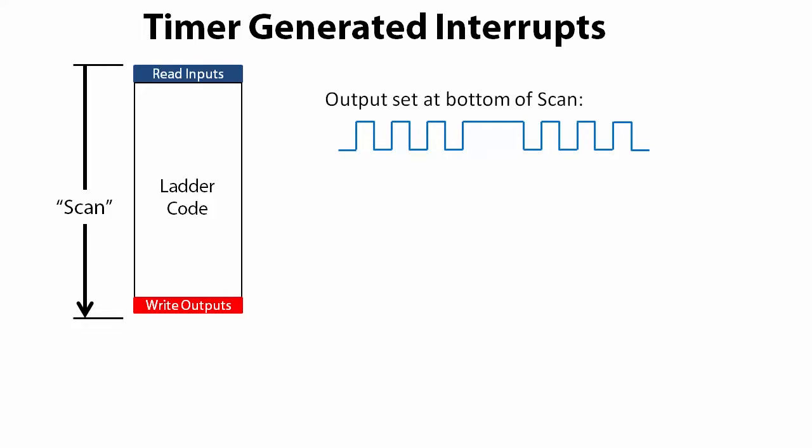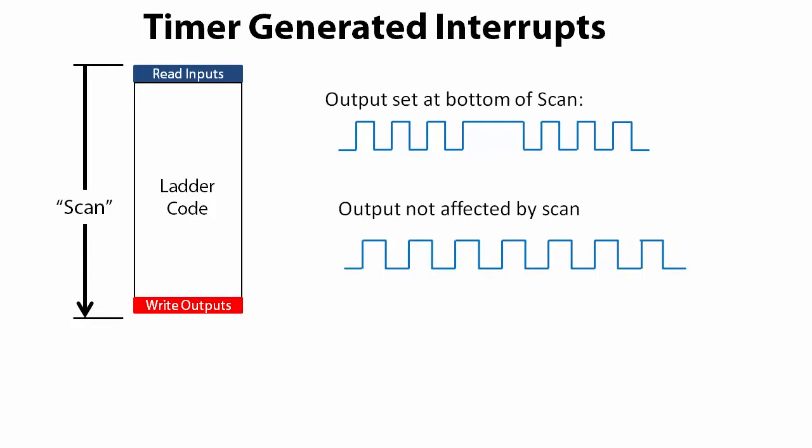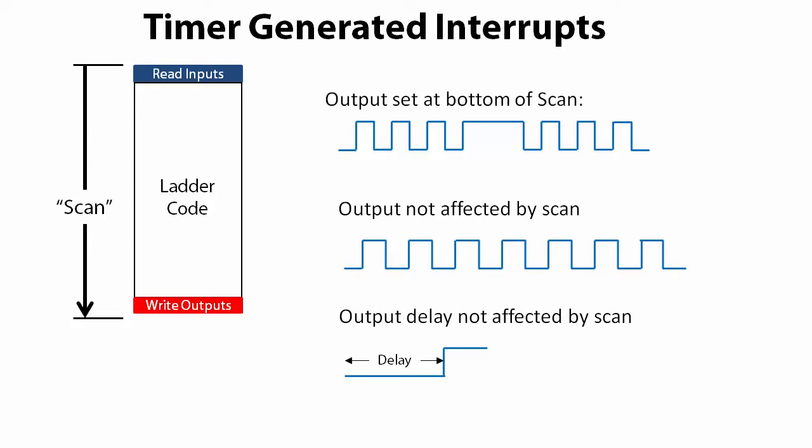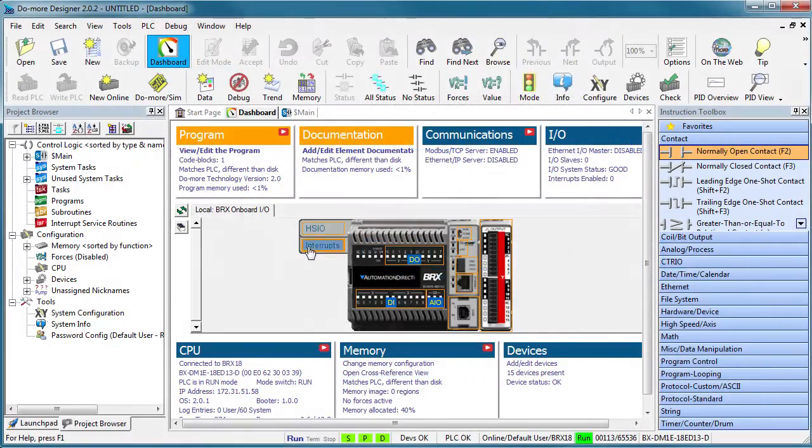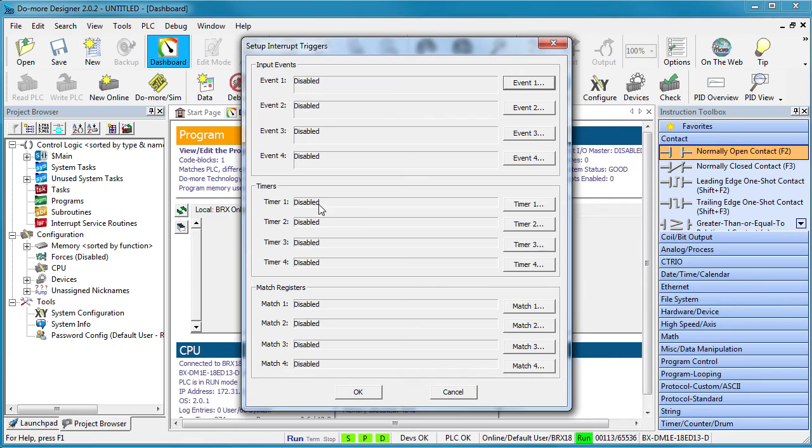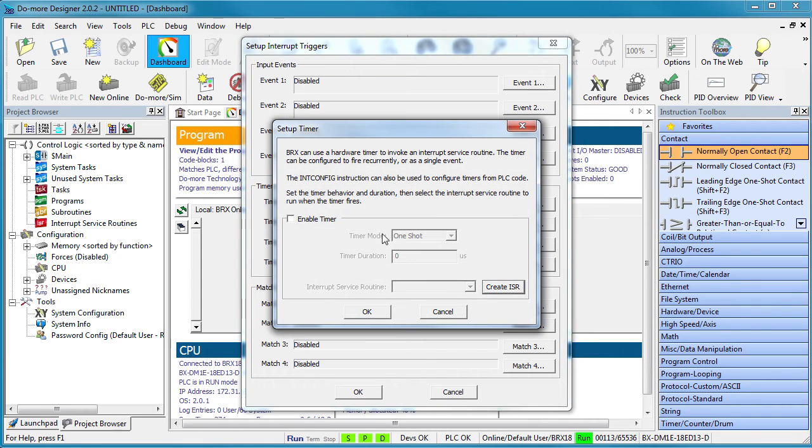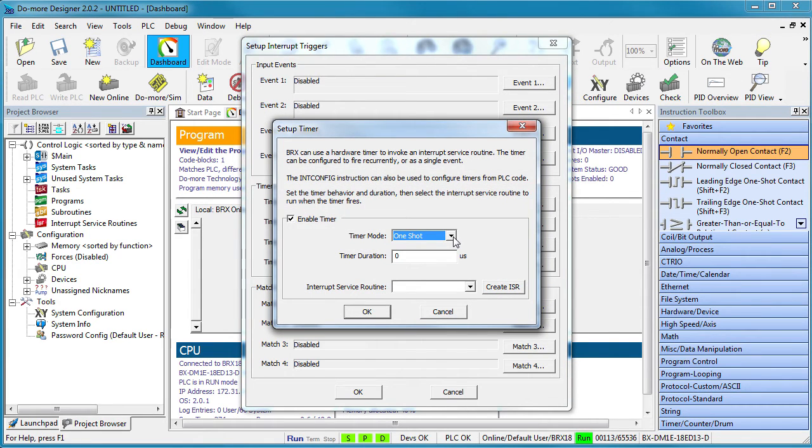We have been using this timer mode to generate periodic interrupt events independent of the scan time. Can you use the interrupt timer to generate just a single super accurate delay? Maybe you want something to happen sometime after an event occurs and it needs to happen right away and not wait for the end of scan. Just use this one-shot mode. The interrupt event will trigger once at the delay time you specify. Easy.